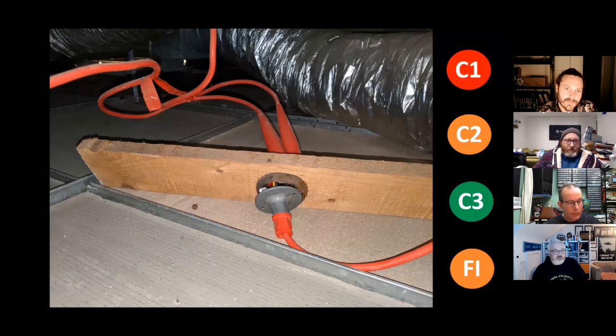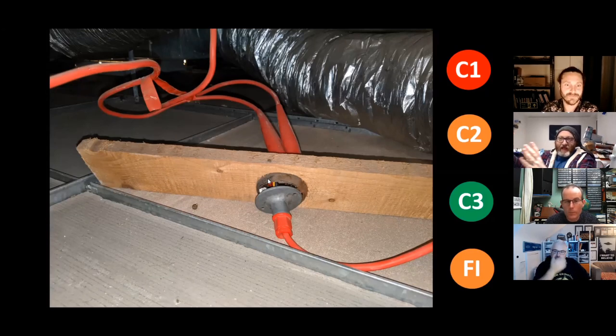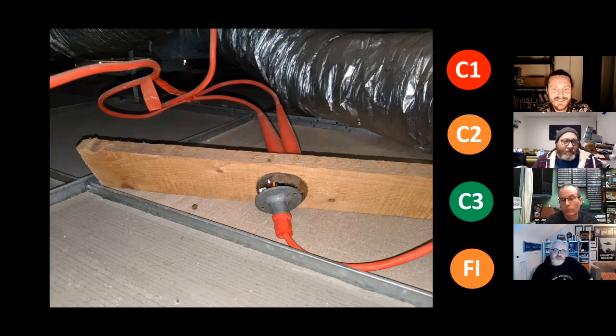Yeah, I'll get the pole. Again, this happens a lot where engineers don't want to play with MI or touch MI, and they'd rather just try to put it out of the way. But think about what we said earlier: in a fire condition, when the structure of the building starts changing, the ceiling may go down, the ceiling may have some structure, or other people working below moving this.